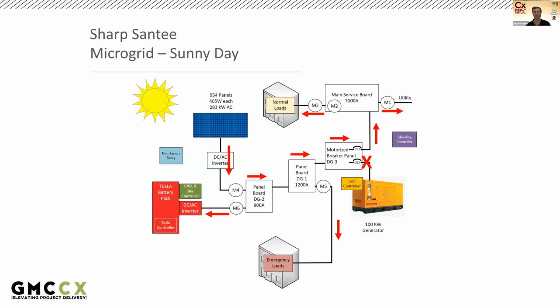So what I'm going to do now is talk through the different operational modes and sequence of operation of the Sharp Santee microgrid system. Starting off with normal operation, a sunny day. The sun is out, and power from the solar array supplies power to DG2 through the DC and AC inverters. Available power at DG2 from the solar panels is used to charge the Tesla battery. Any extra power then goes to DG1, which serves power to the emergency loads. Then any more available power goes to DG3, which is the two circuit breakers, CB1 and CB2.